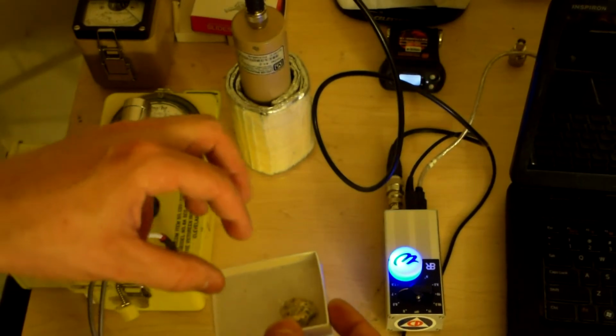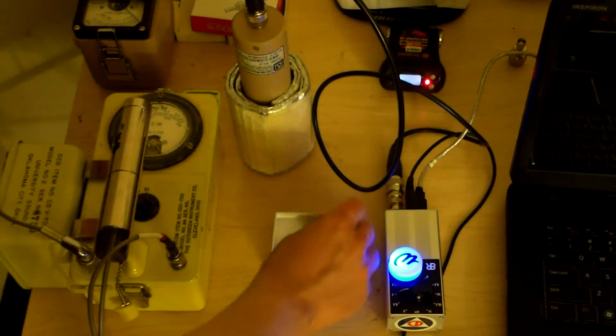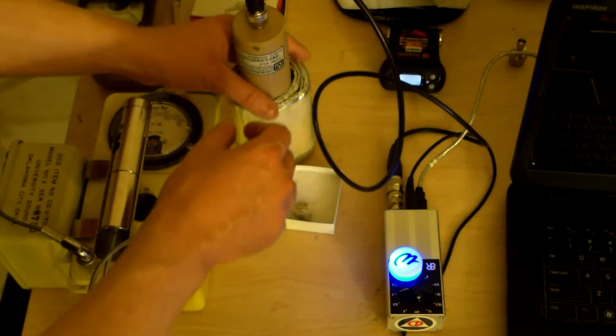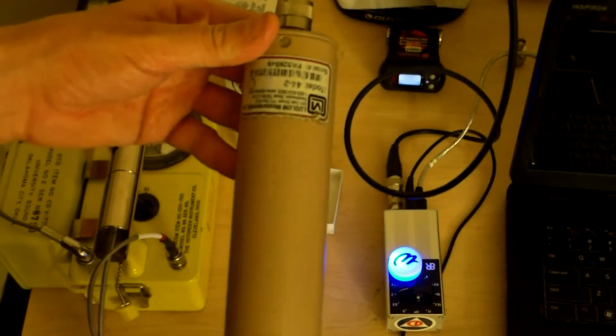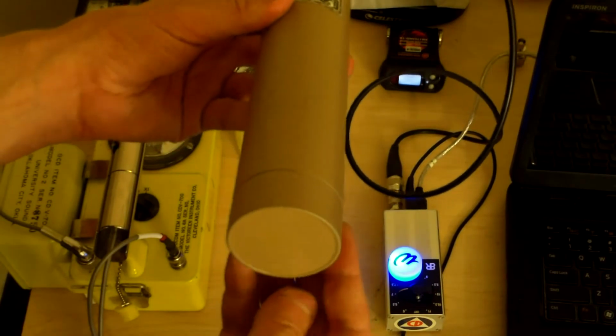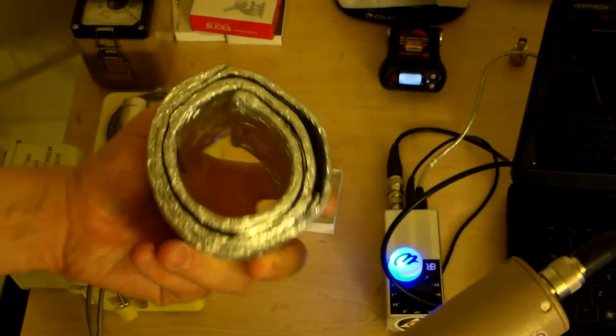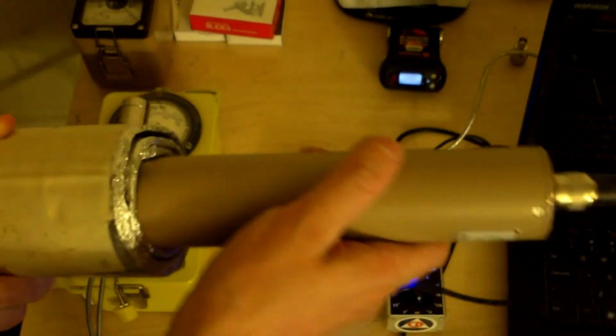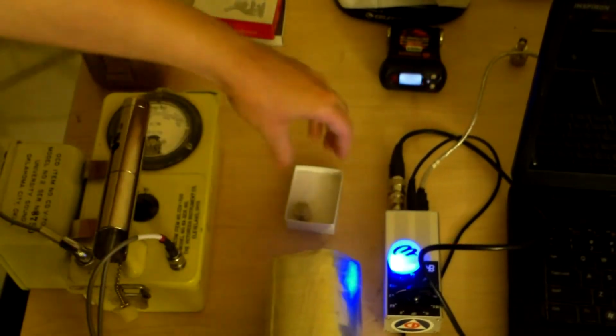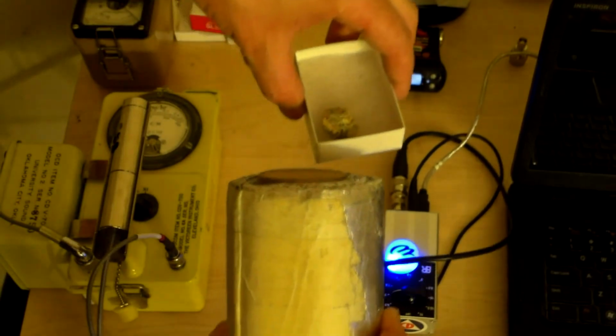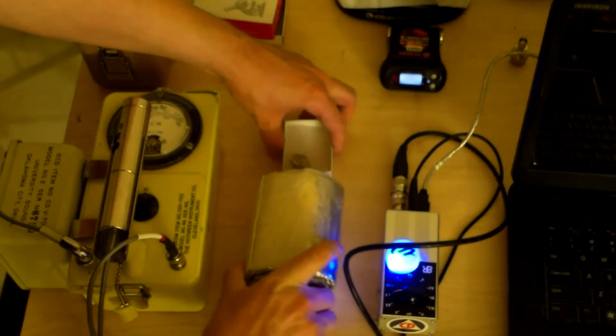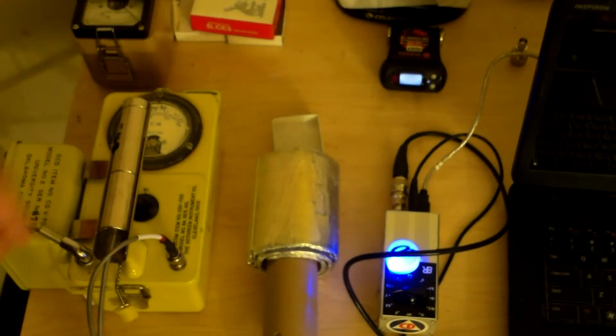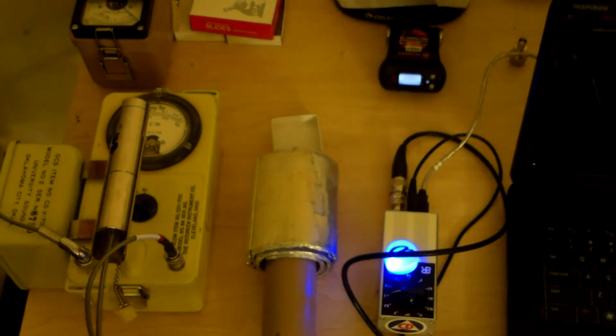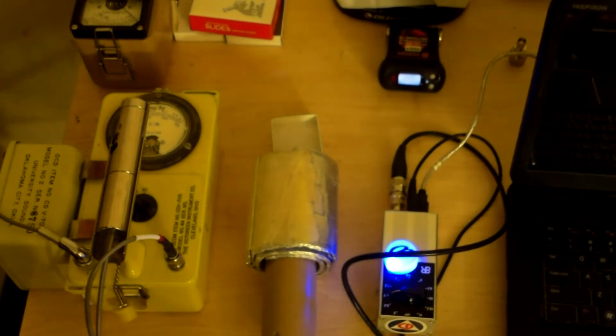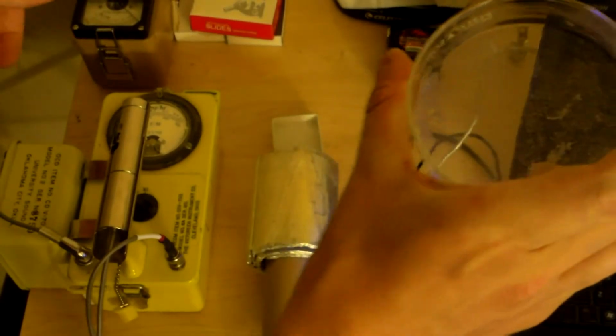Now this sample. What we're going to do is put it down, and take this 1-inch probe. This is a Ludlum model 44-2 1-inch sodium iodide scintillation probe. This is a big block of lead pretty much in here. This will cut down some of the background. We're going to put this up against it so it's pretty close. See? Pretty close. Like that. And let's see, if I have another one of these bottle caps sitting around, we're going to use a bottle cap, and we're going to use a piece of Pyrex. Here's a piece of Pyrex dishware right here.